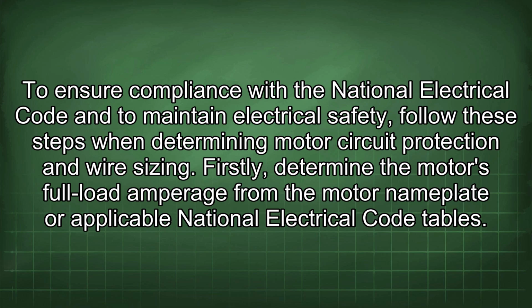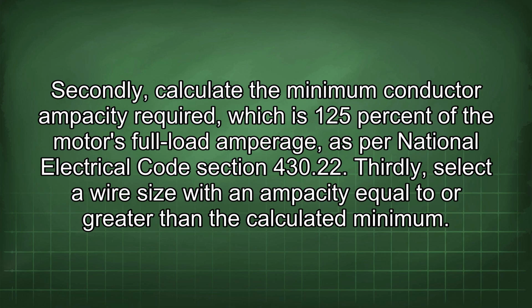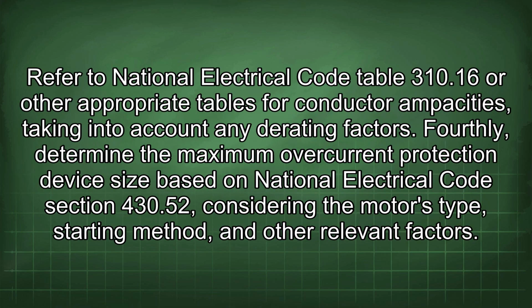Firstly, determine the motor's full load amperage from the motor nameplate or applicable National Electrical Code tables. Secondly, calculate the minimum conductor ampacity required, which is 125% of the motor's full load amperage, as per National Electrical Code Section 430.22. Thirdly, select a wire size with an ampacity equal to or greater than the calculated minimum. Refer to National Electrical Code Table 310.16 or other appropriate tables for conductor ampacities, taking into account any derating factors. Fourthly, determine the maximum overcurrent protection device size based on National Electrical Code Section 430.52, considering the motor's type, starting method, and other relevant factors.